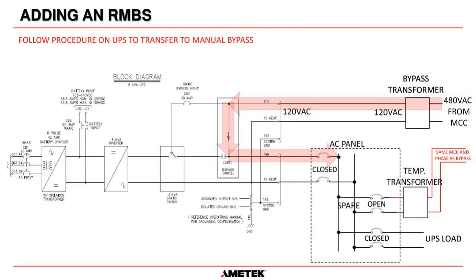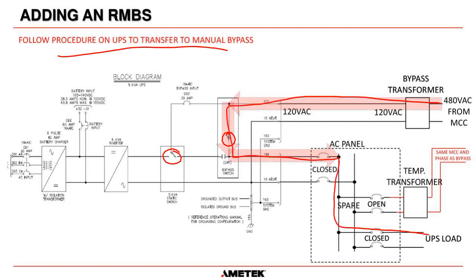Okay, so now remember, everything that we've done previously is with the UPS on inverter to load. Everything was running as normal. So now we have to follow the procedure on the UPS to transfer to manual bypass. On the UPS, you just follow the placard on the front and follow the procedures there. One step will be to put the static switch in bypass to load, and the last thing will be to put the manual bypass switch in bypass to load. Once you do that, you will have power flowing from here down here and then out to your UPS loads. Okay, so the UPS is now in manual bypass.